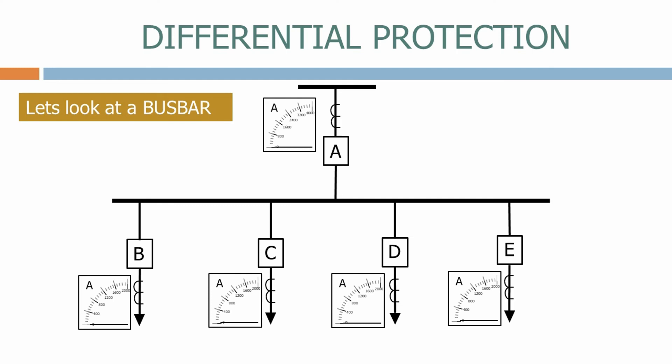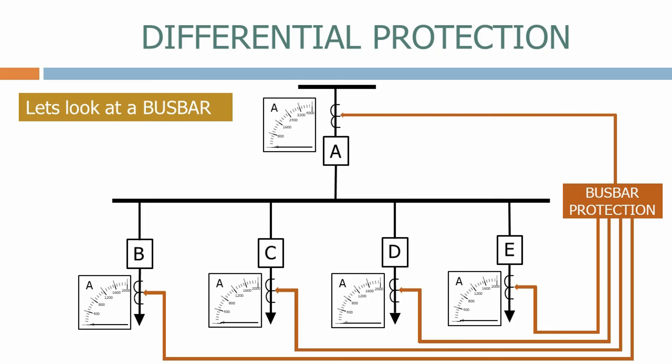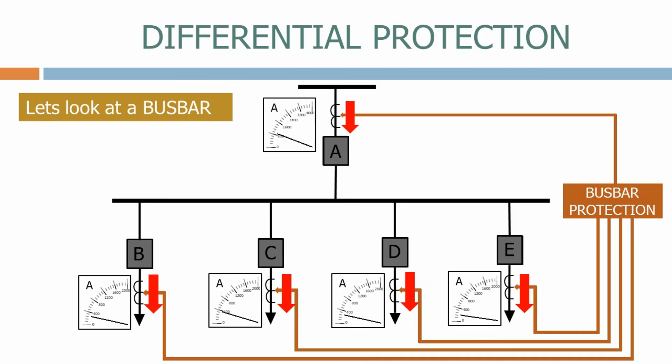Let's look at a busbar. Here we have an electrical system with an incomer feeding a busbar connected to four feeders. A busbar protection scheme needs to measure all of the currents flowing into and out of the busbar. The busbar differential scheme therefore measures the currents on all incomers and feeders. As expected, the current magnitudes on each circuit vary continuously as the loads change, but the sum of the currents flowing into and out of the busbar will always equal zero.